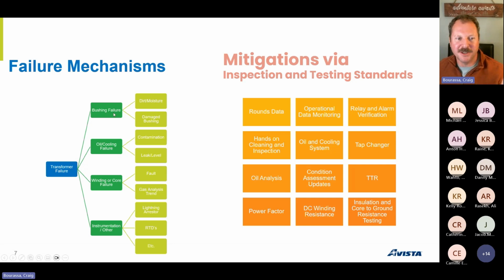You also have bushings. You could have damaged bushings or dirt and moisture in them. The best way to test it is to do a power factor test - put some current into it when it's isolated and look for leakage. So it's really going through each subcomponent of each asset at your plant and looking at how it can fail.